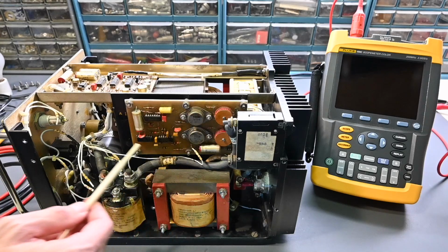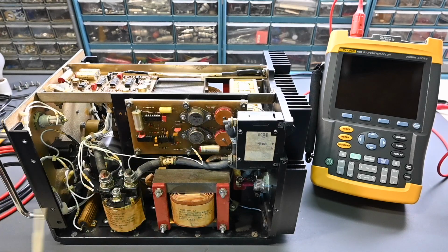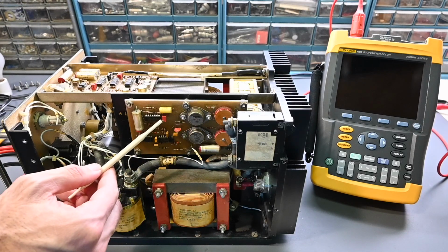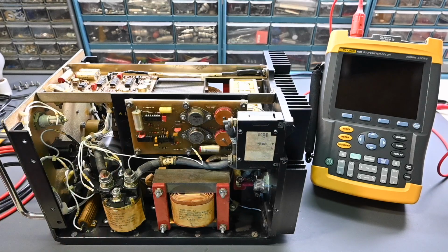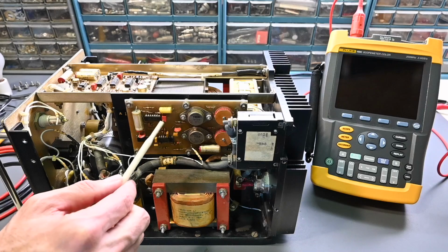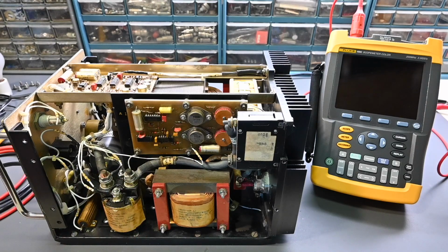Knowing this board is driving those SCRs, I tried adjusting this trimmer potentiometer because the frequency and voltage were both a little low. I gave it just a tiny turn, figuring I could always reset it back, and in no time it brought the frequency right up to 60 hertz, which was great to see. It clearly affects the frequency, and it makes sense that this would be the oscillator setting that frequency.